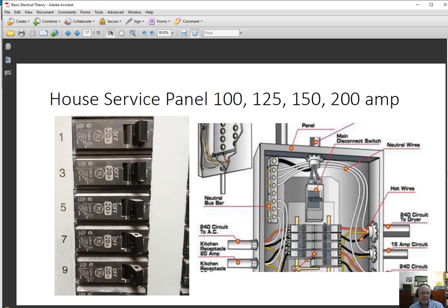Moving to the service panel: on the left-hand side is a series of circuit breakers — these are all 20 amp circuit breakers, and in every case they are individual breakers. You'll notice there's a hole in the side so you can put a pin that goes down through two of them and makes each work together — you can't turn one off without the other getting turned off as well. That's so you can combine them for 240 volt appliances. That's a little unusual now; instead, people buy breakers that are already joined together.